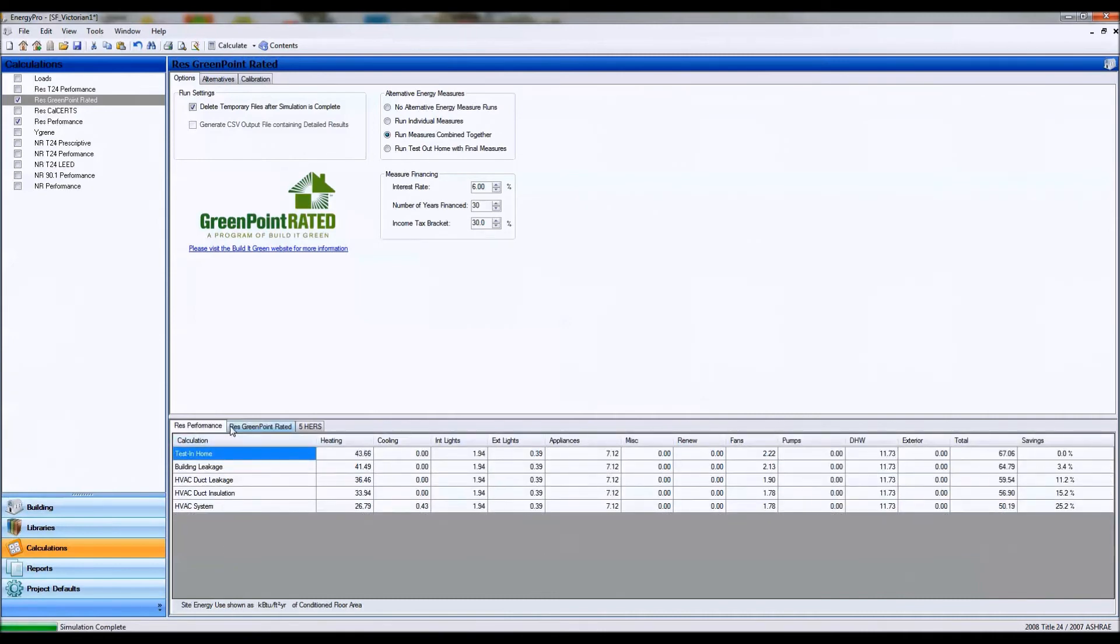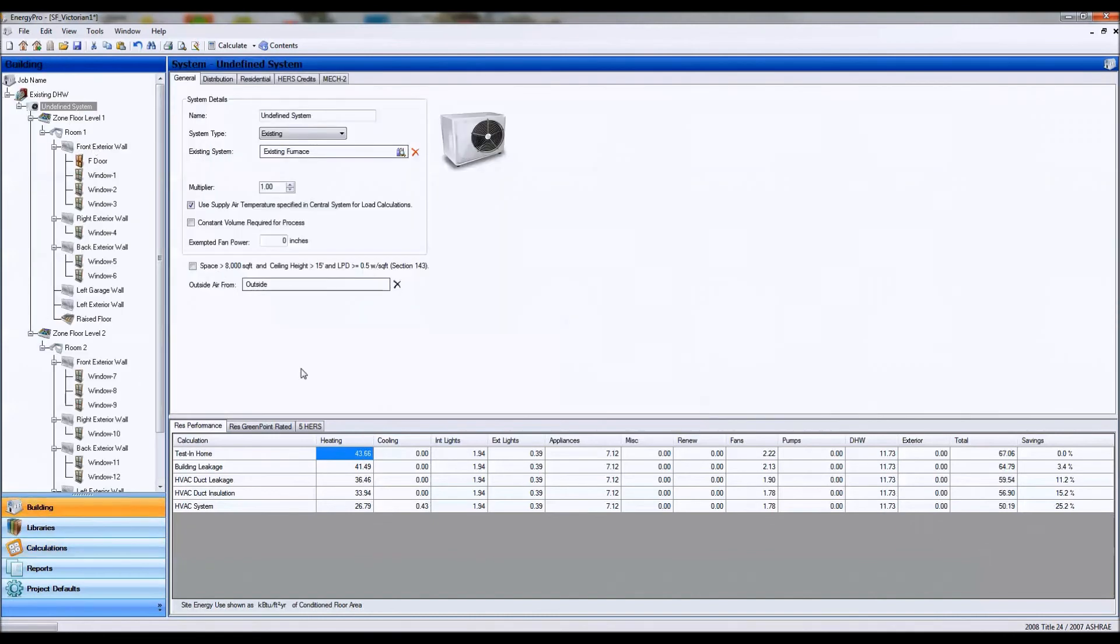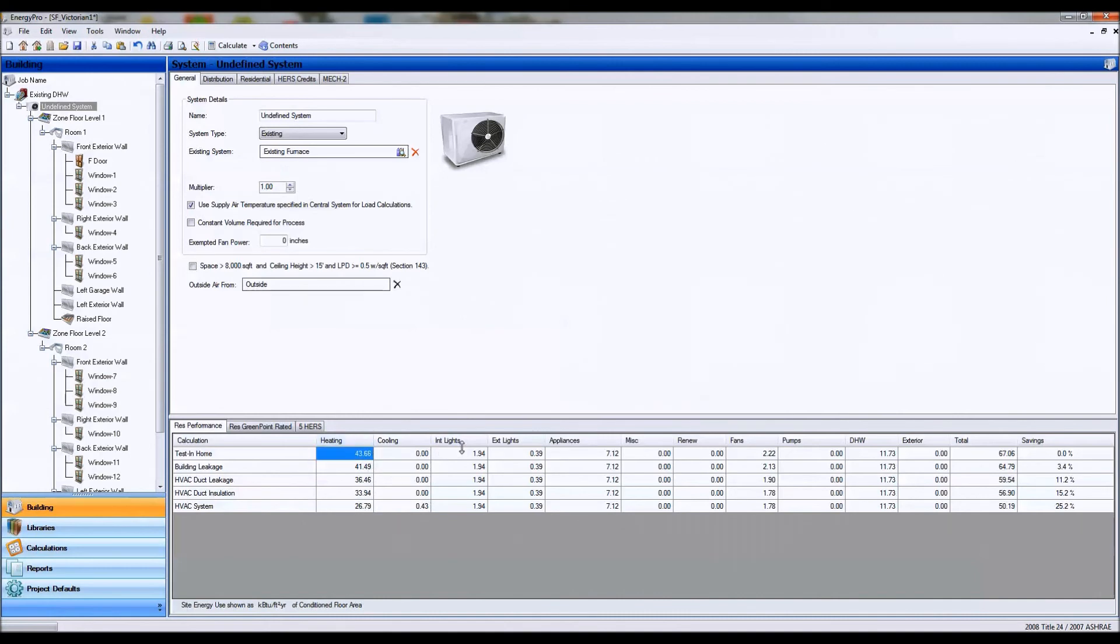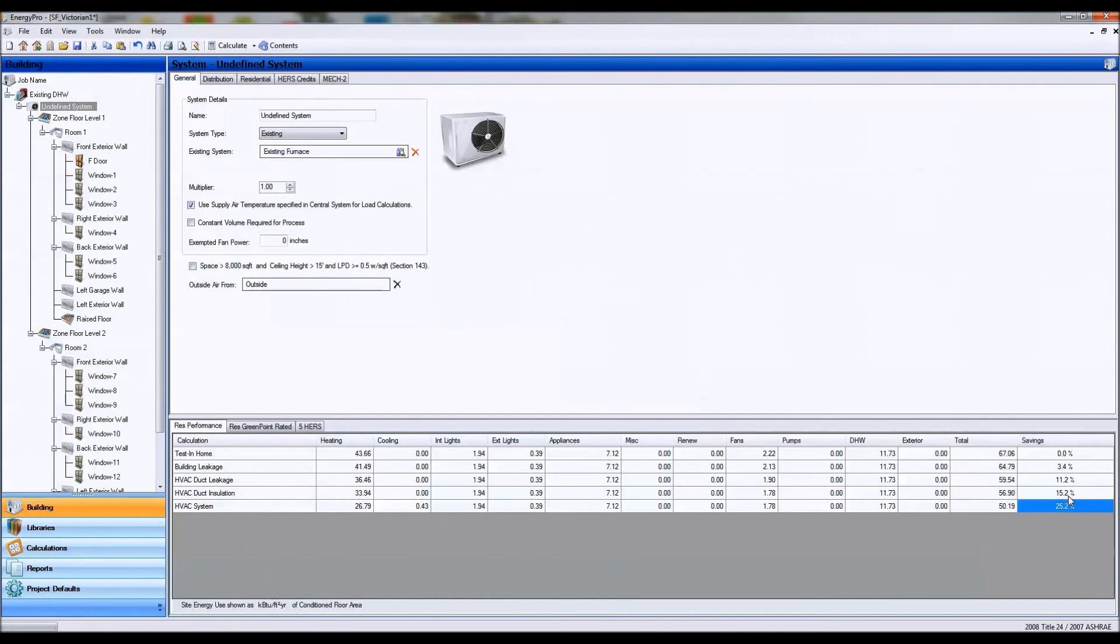Okay, so let's go ahead and look at our res performance calculation first. As you can see, we have our baseline building load here, and this is based on kilobtus per square foot per year. It gives us a savings on each of our heating, cooling, and our different end uses. And it will give us a site savings calculation in the end. So as you can see, I'm getting a 25% site savings which is at my meter.